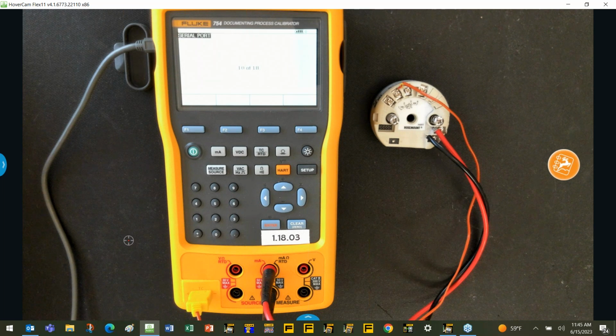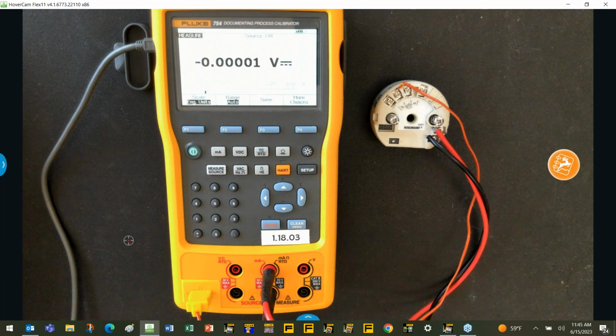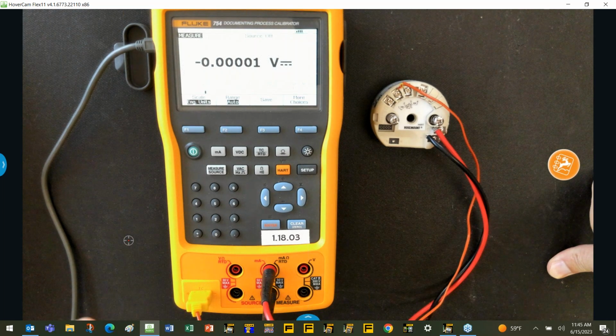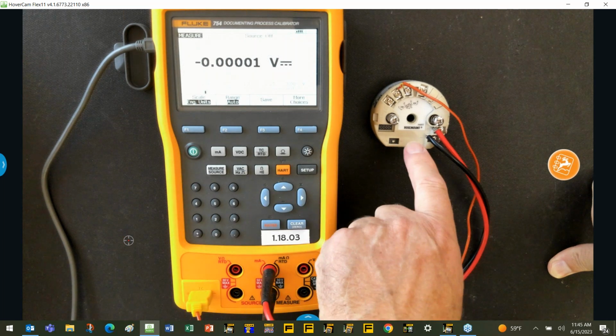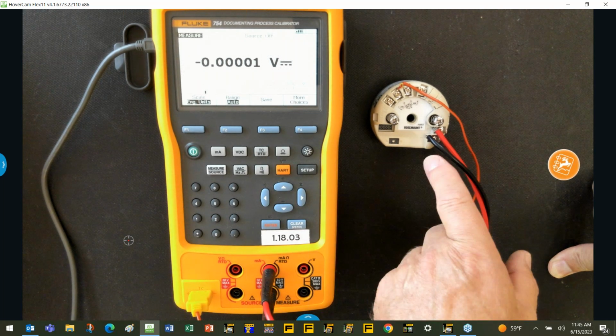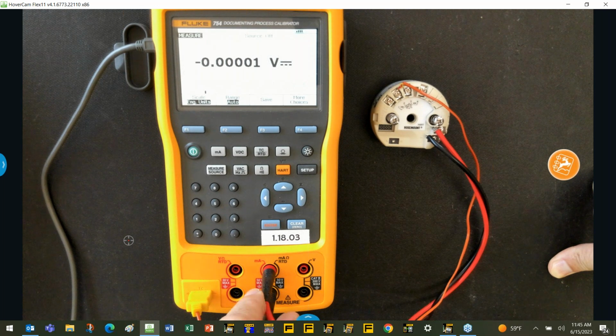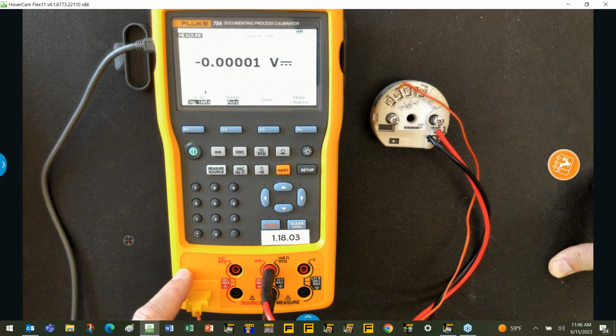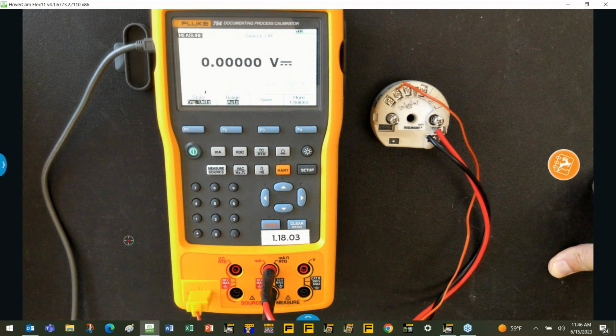And there it goes right there. So once that's downloaded, now we're going to go ahead and put the calibrator into HART mode. Now you'll see I'm connected up to the 644 transmitter, and I've got my plus and minus milliamp measure and 24 volt output and HART through this cable. And then I've got a thermocouple type K in this case connected to the calibrator.